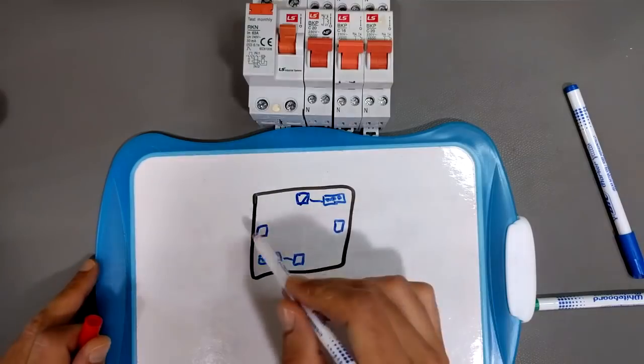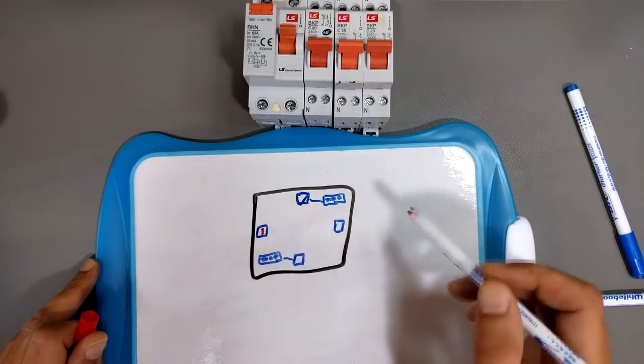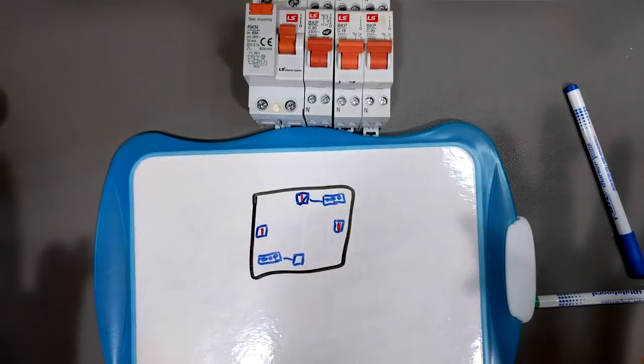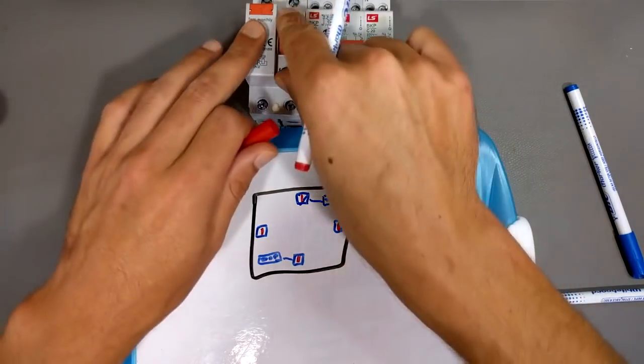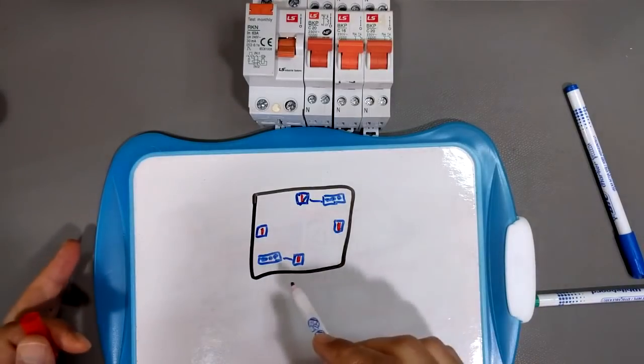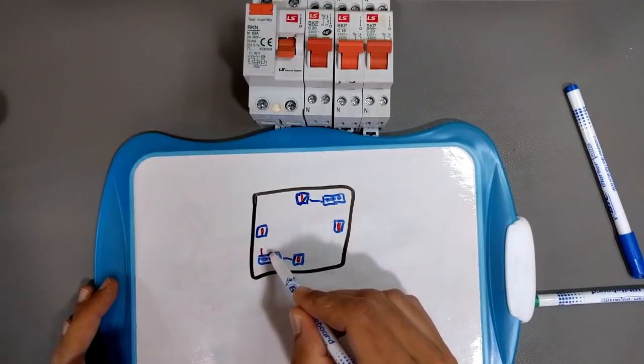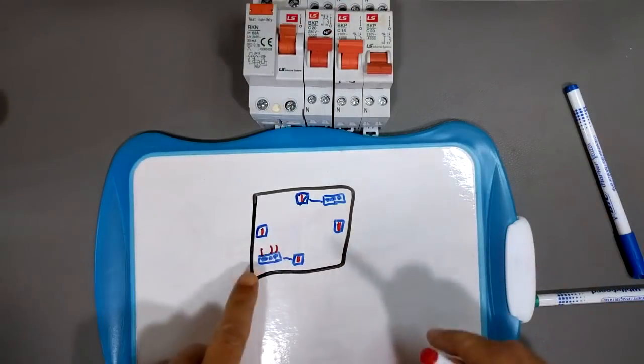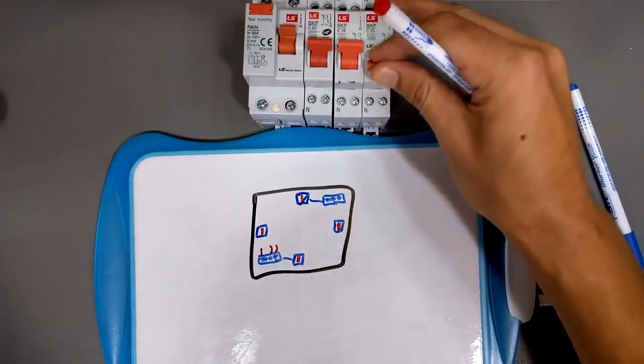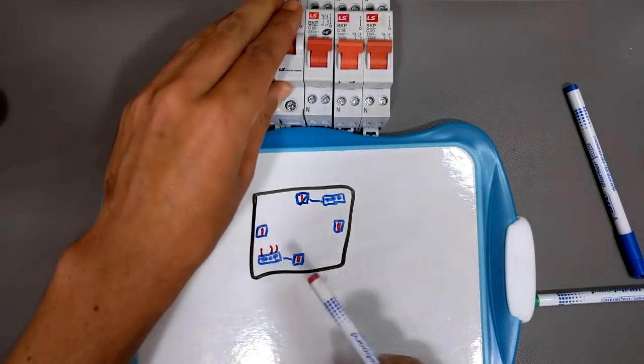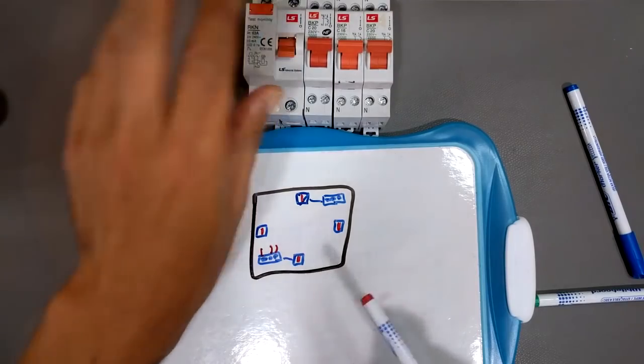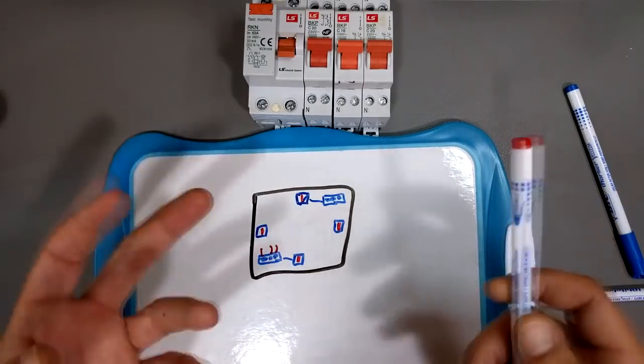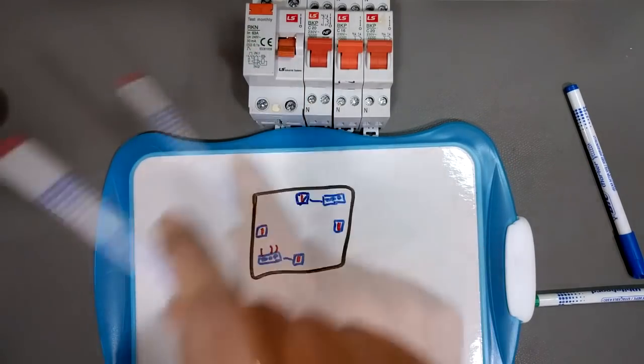So, first you plug this one back in. Then you plug this one back in. Wait a few seconds. Then you plug this back in. Nothing happens. Then you plug this one back in, and when you do, it trips. Right? Okay. Then what you do is you go back and you unplug these three things. Unplug all of them and plug just the power strip in. Go back, flip this on. With nothing plugged into this power strip and just the power strip plugged into the wall, flip this on. It is entirely possible that when this power strip with nothing plugged into it is plugged into that outlet, your differential breaker will trip. I have actually seen this before. You can actually have a power strip that is screwed up with nothing plugged into it that has some kind of fault inside that will cause leakage current that will cause your breaker to trip.